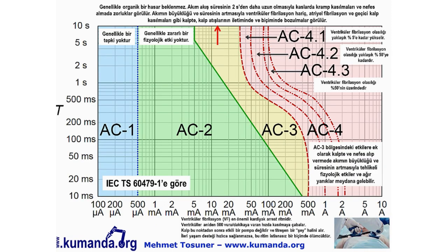IEC 60479'daki grafik insan üzerinden geçen akım ve süreye bağlı olarak insanda oluşan etkiyi gösteriyor. AC1 alanı 500 μA'ye kadar — genellikle tepki yok. AC2 alanı 500 μA'den başlayıp süre uzadıkça küçülüyor — zararlı fizyolojik etki genellikle yok. AC3 alanında (sarı) organik hasar beklenmez ancak akım 2 saniyeden uzun sürerse kaslarda kramp, nefes almada zorluk ve kalp atışlarında bozulmalar görülür.